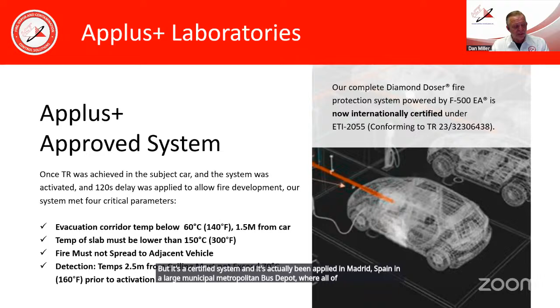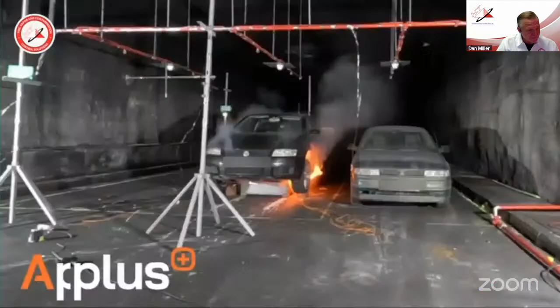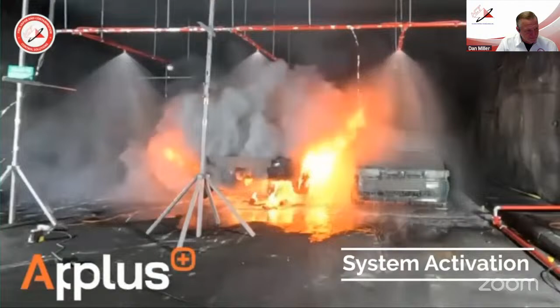A little bit more about the test. Part of this is the system had to activate by the time the temperatures reached 160 degrees Celsius at the ceiling. They actually let it burn for quite a while to get into thermal runaway, and then they manually activated it. But the indication was that it would activate before that. And that was a test of the detectors themselves.